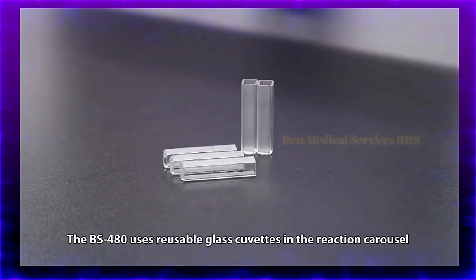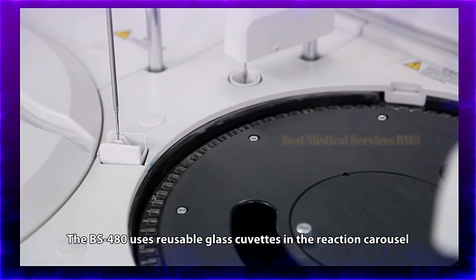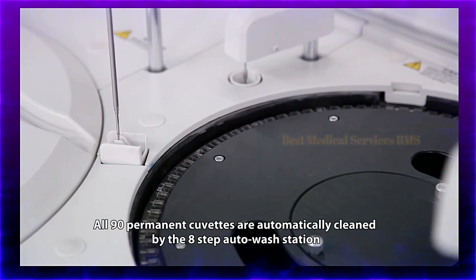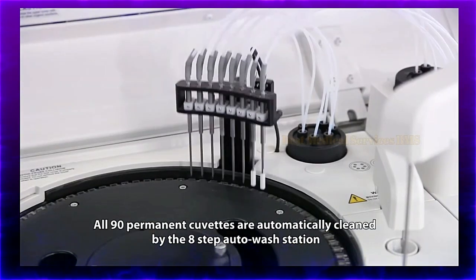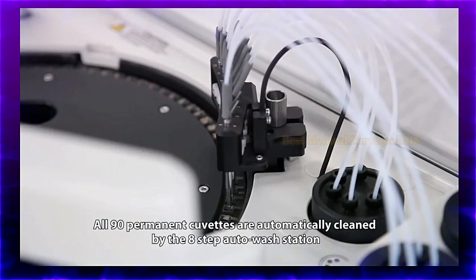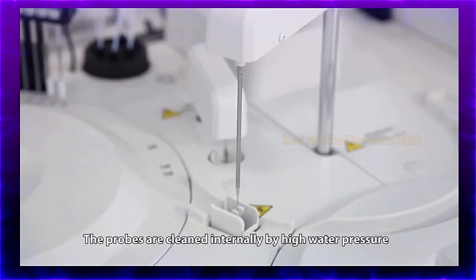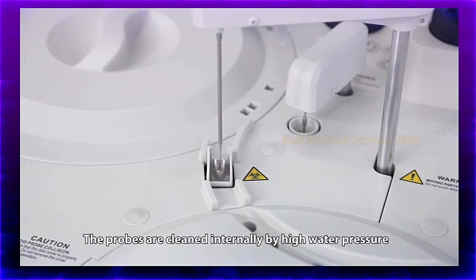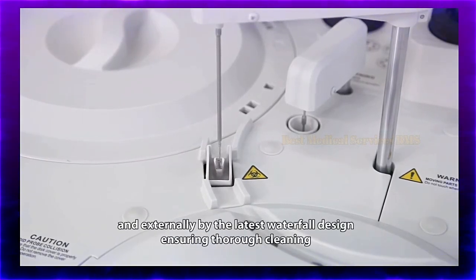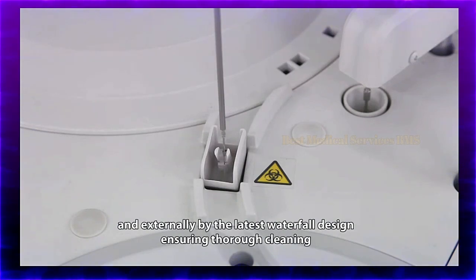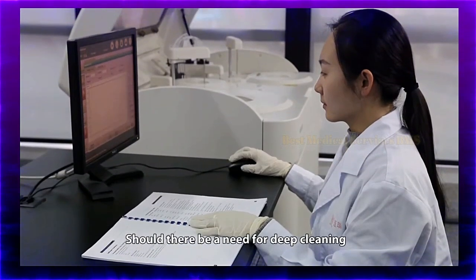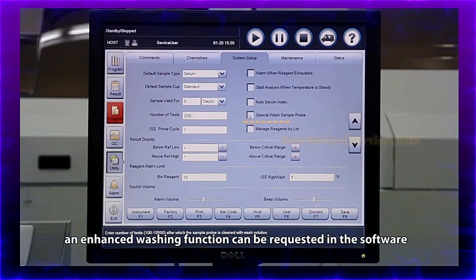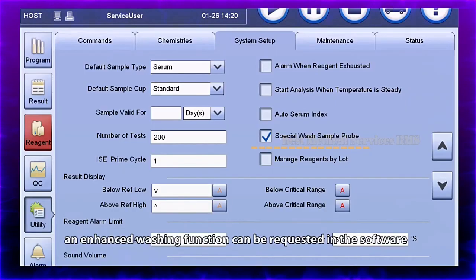The BS-480 uses reusable glass cuvettes in the reaction carousel. All 90 permanent cuvettes are automatically cleaned by the 8-step auto wash station. The probes are cleaned internally by high water pressure and externally by the latest waterfall design, ensuring thorough cleaning. Should there be a need for deep cleaning, an enhanced washing function can be requested in the software.